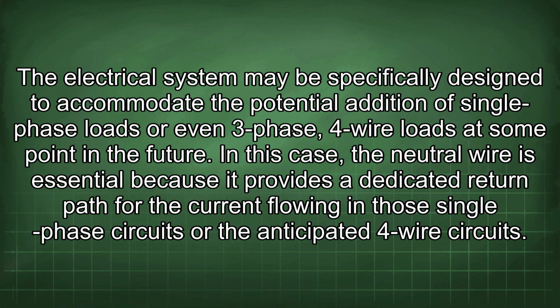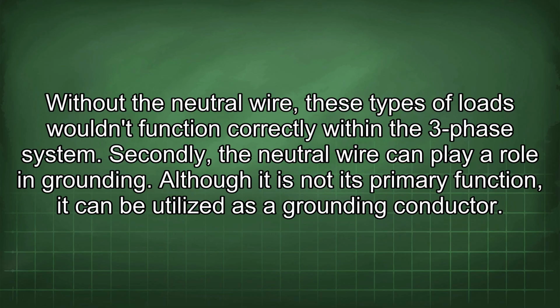In this case, the neutral wire is essential because it provides a dedicated return path for the current flowing in those single-phase circuits or the anticipated four-wire circuits. Without the neutral wire, these types of loads wouldn't function correctly within the three-phase system.